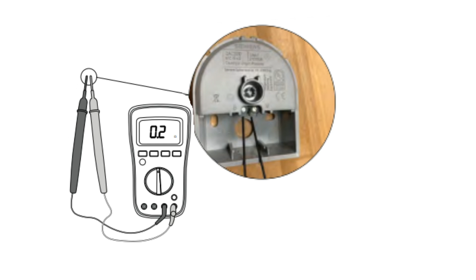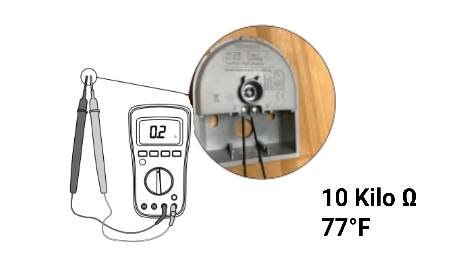If you don't find a short, then see if the resistance of the temperature sensor is normal, and if not, then replace the temperature sensor. A normal resistance will read 10 kiloohms at 77 degrees Fahrenheit. Replace the control board if the resistance of the temperature sensor is normal.